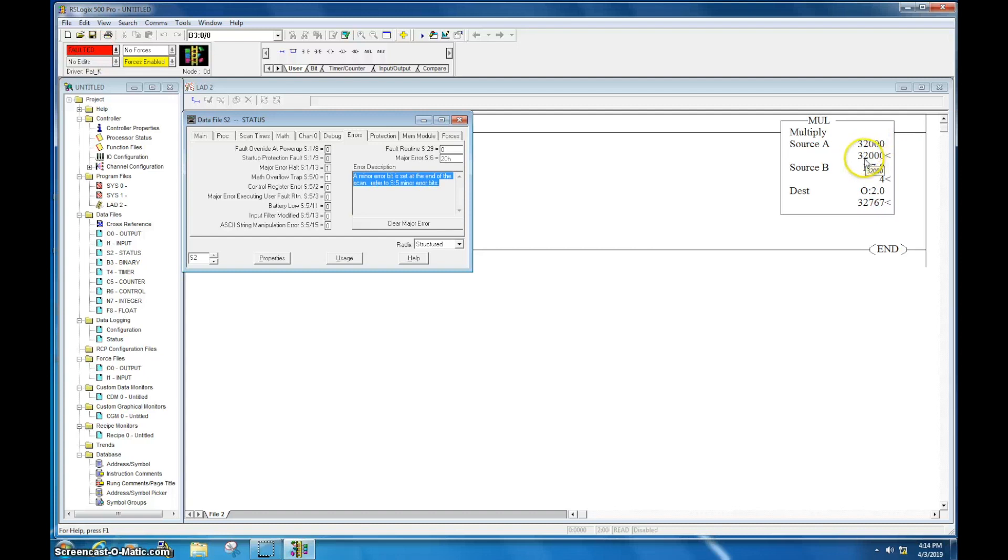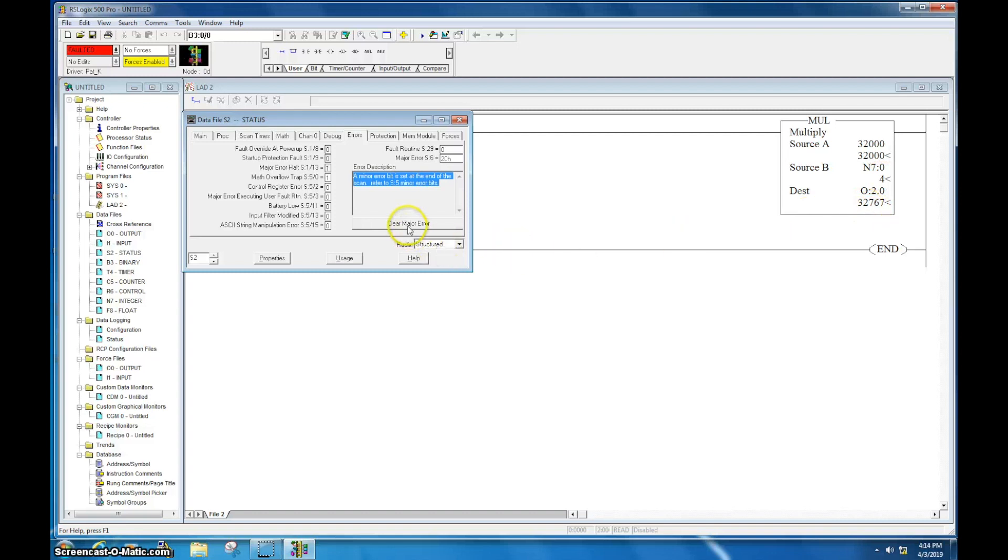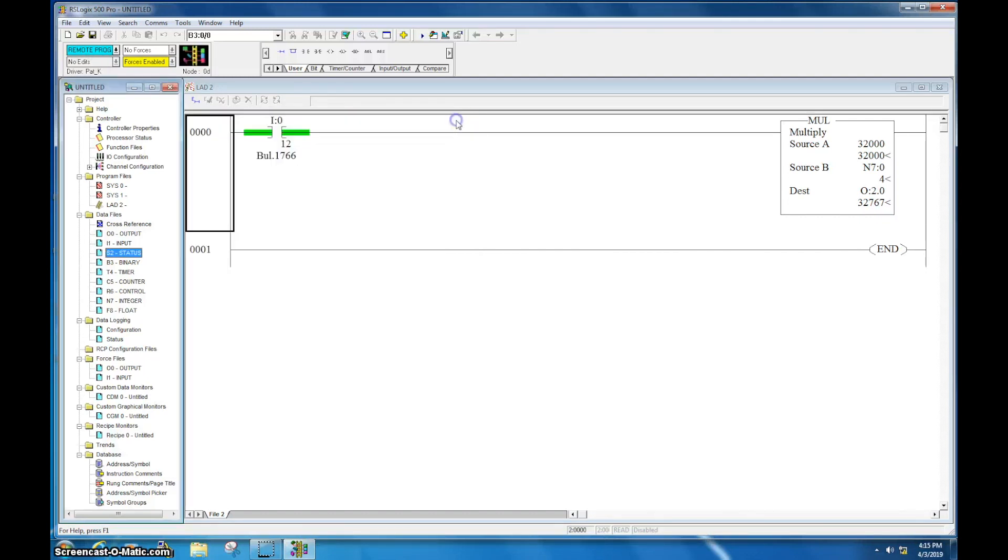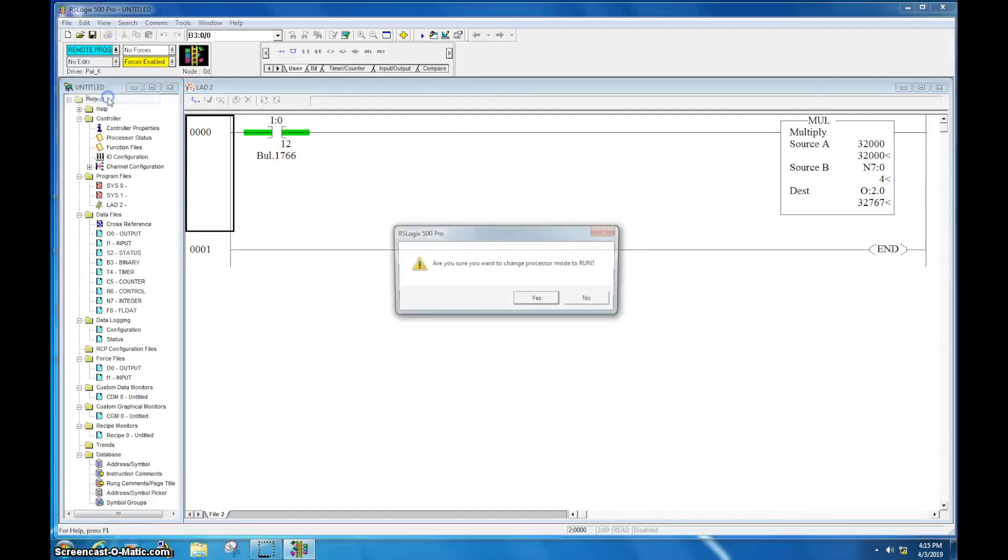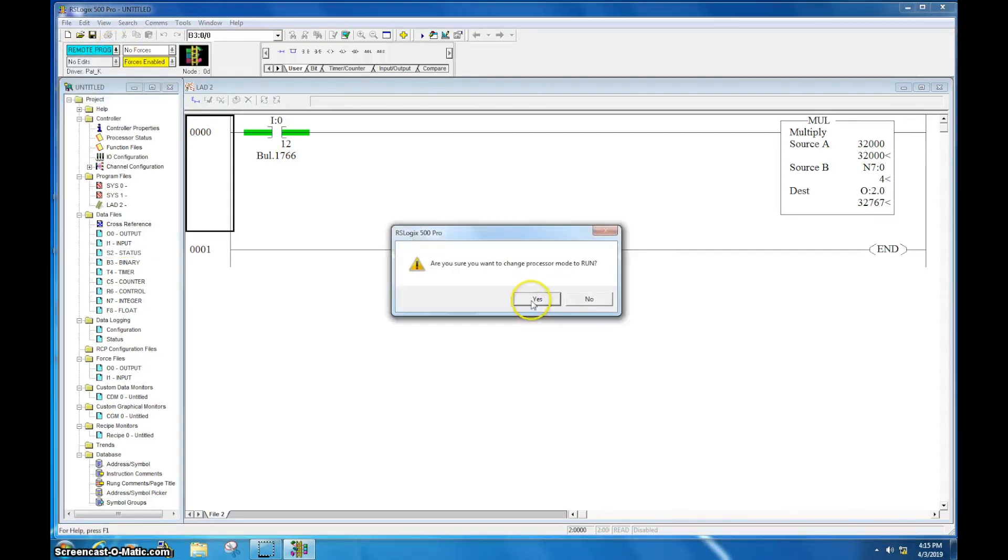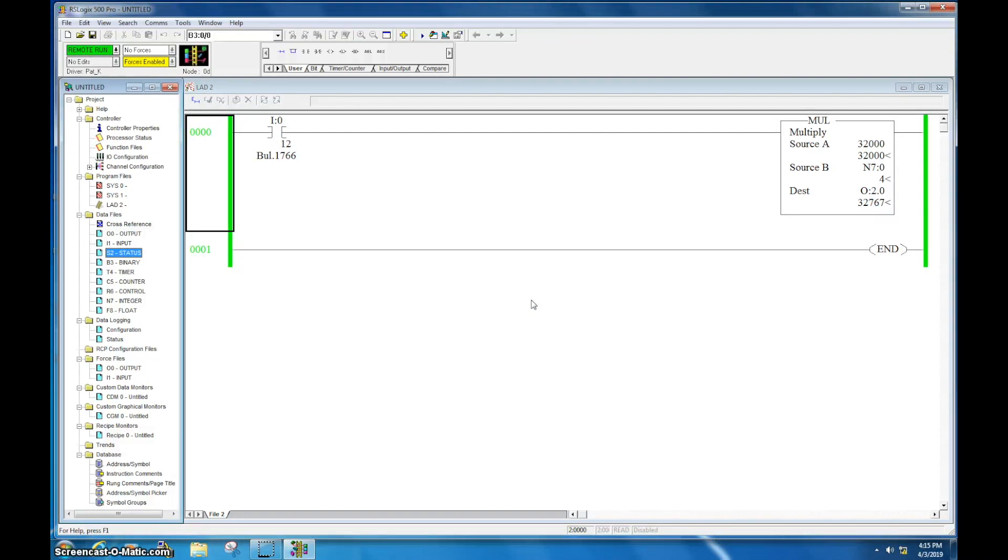In this case, to create the fault, I just took 32,000, multiplied it by 4, which is well over that. That faulted this out. So, I can come here, I'm going to set clear major error. I'm going to close this out, I'm in remote program. If I come over to here, I can now go back into run mode, and I'm ready to rock and roll. Okay? And you can see on my PLC, that fault is gone.